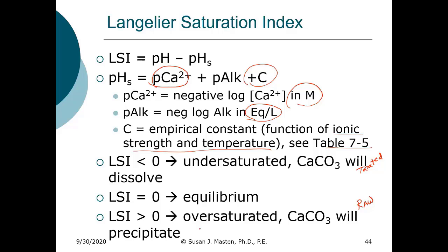In 481, for those of you that have taken it or will take it, they talk about it in terms of activity. Here, that's incorporated into the LSI equation. So if the LSI is less than 0, that means that it's undersaturated and calcium carbonate will dissolve. If it's equal to 0, you're at equilibrium. If it's greater than 0, you're oversaturated.